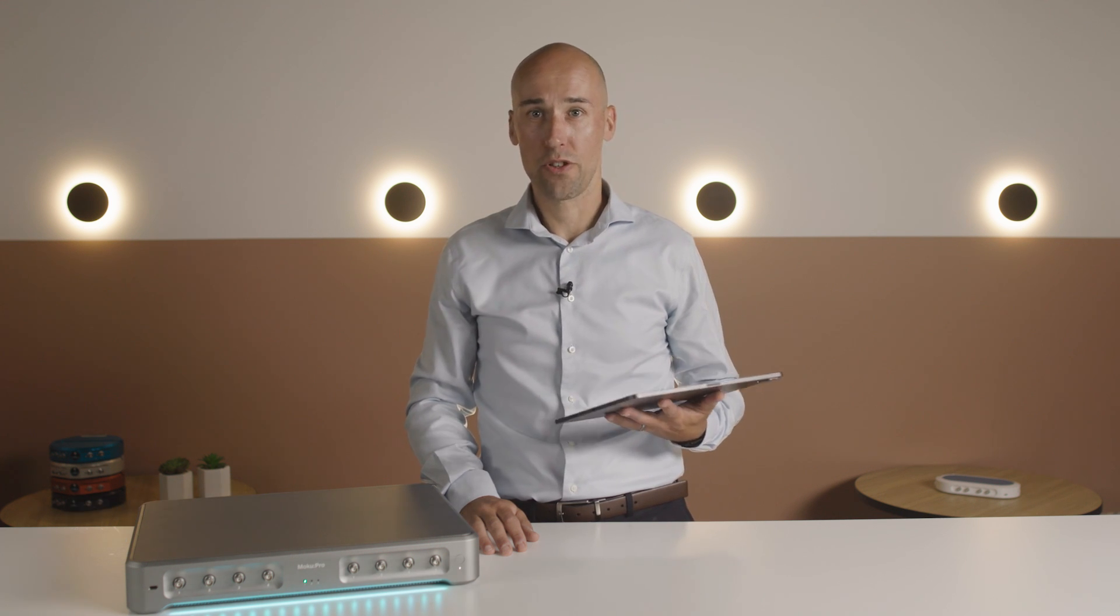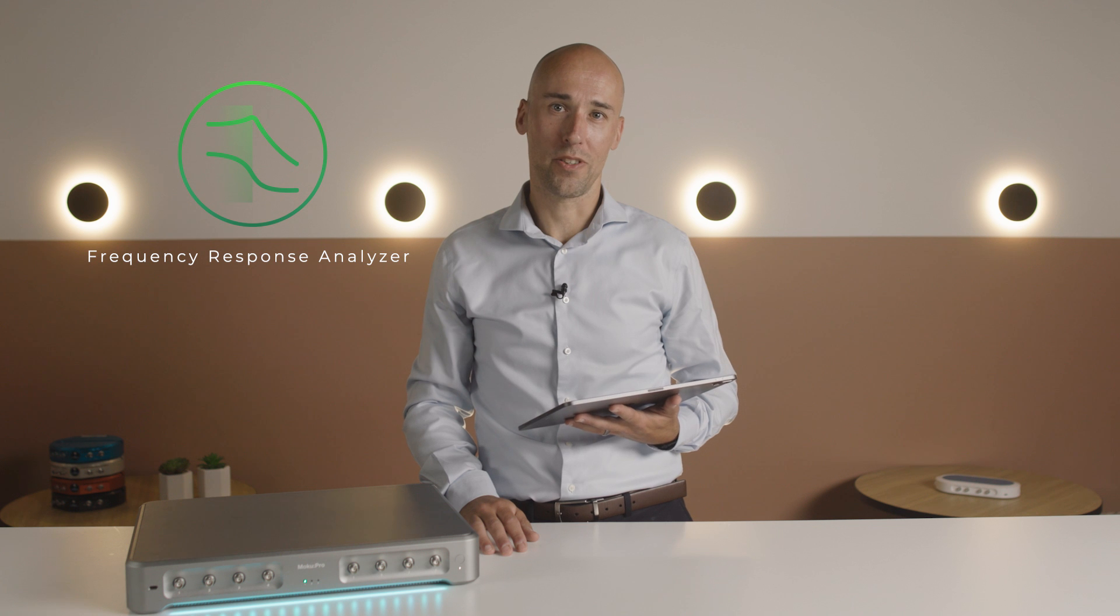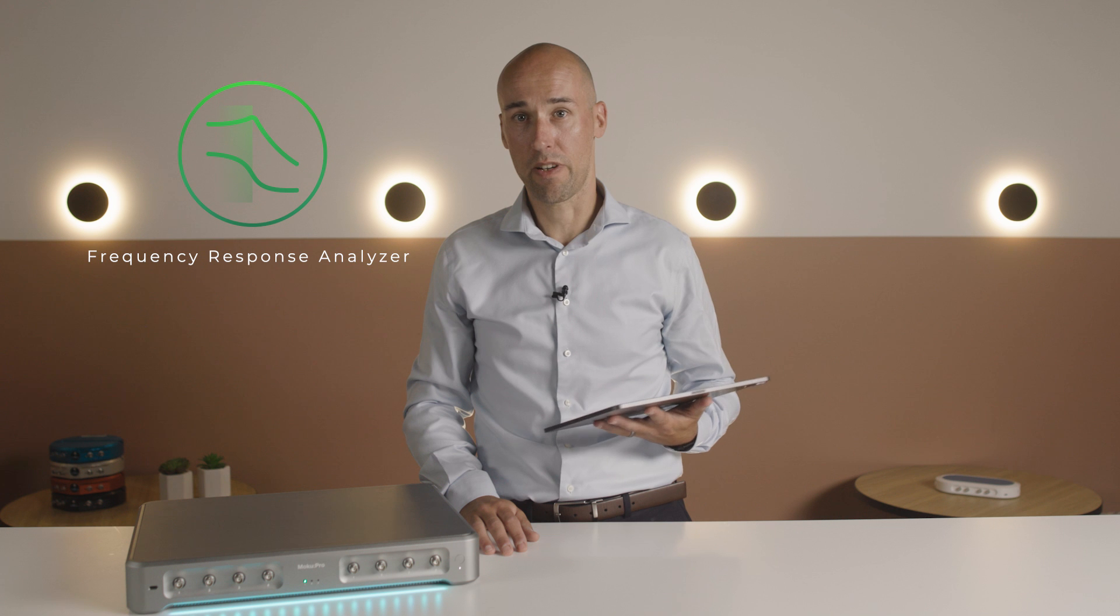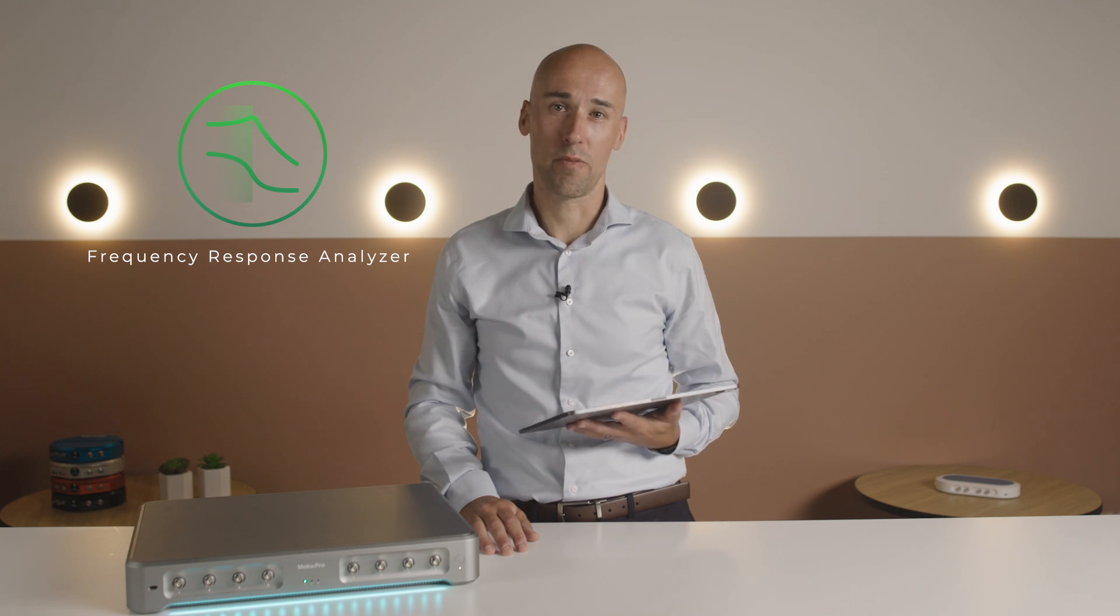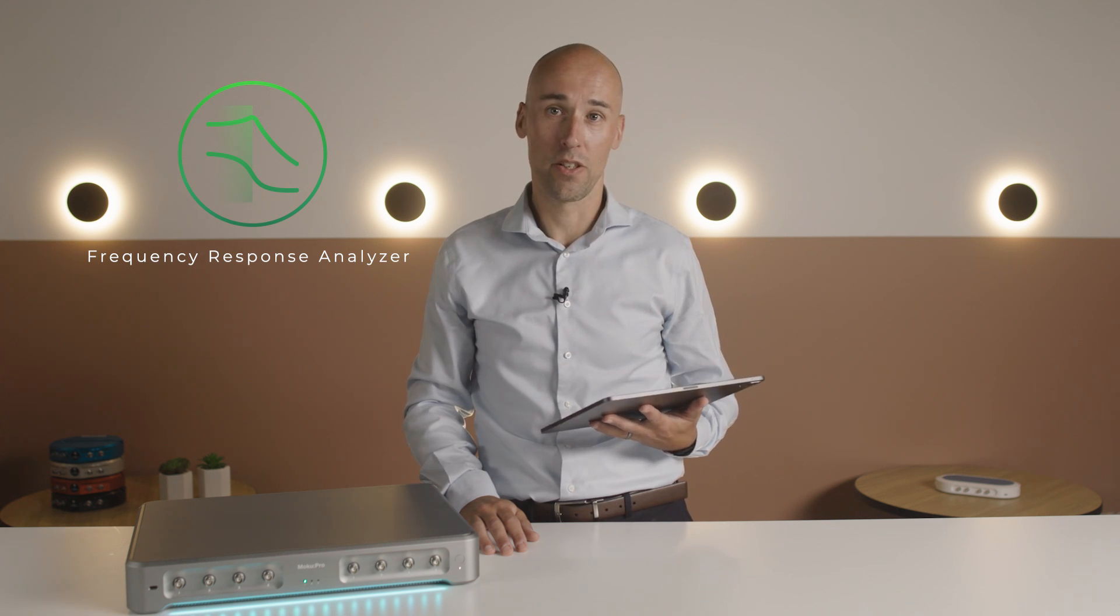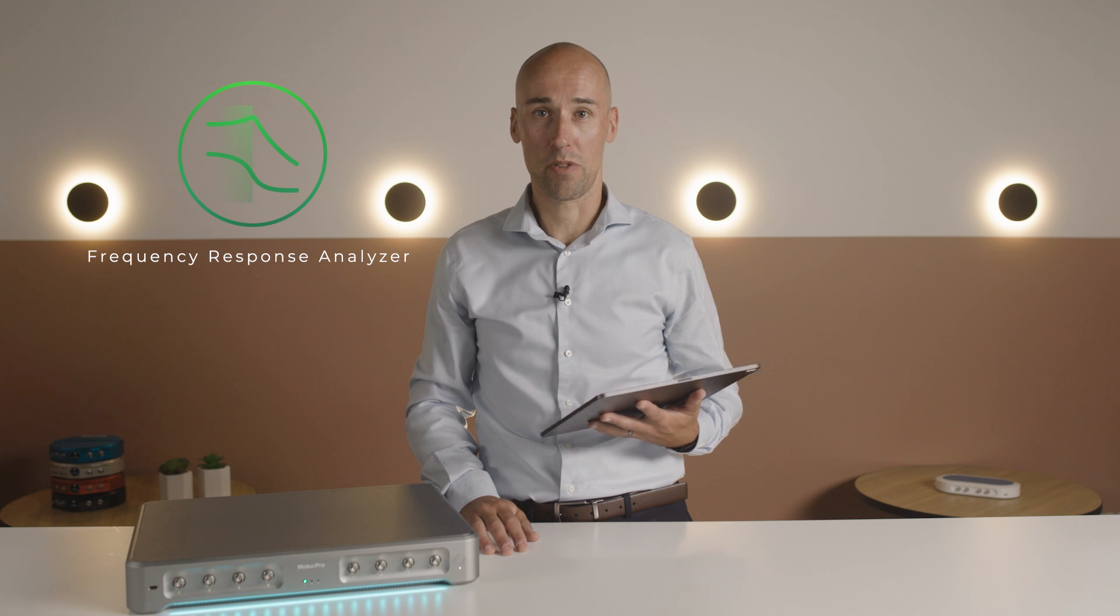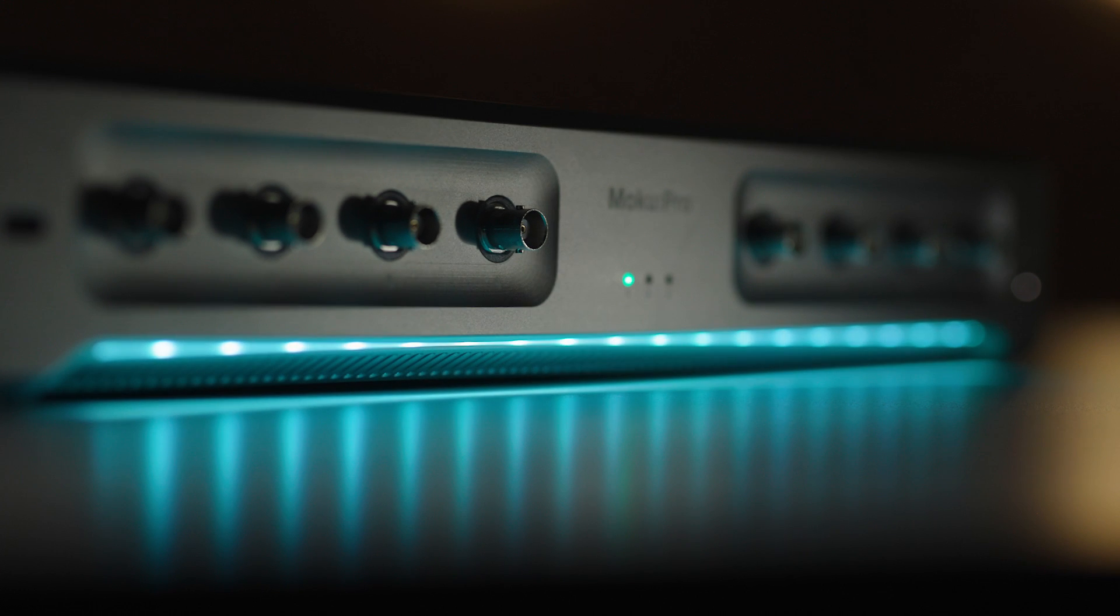In this video, I'm going to show you how the Moku Pro Frequency Response Analyzer enables you to quickly and easily measure the frequency response or transfer function of a device under test from 10 millihertz to 300 megahertz with a linear or logarithmic sweep sine output. Moku Pro is equipped with four inputs and outputs enabling differential or ratiometric measurements.